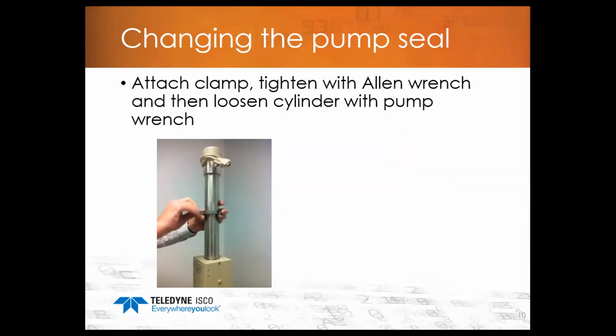Now here's where, if you do have the wrench package, you can attach your clamp to the cylinder. Basically the clamp is 2 halves. You clamp each half around the cylinder, and then there's 2 Allen bolts in the clamp, and you use your 1/4 inch Allen wrench to tighten the clamp to the cylinder. You want to get it on there fairly tight so that it doesn't slip on you when you're trying to remove the cylinder.